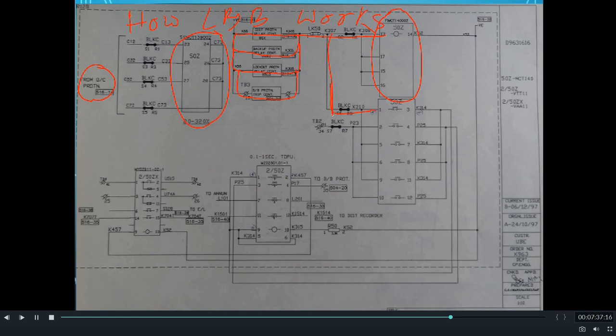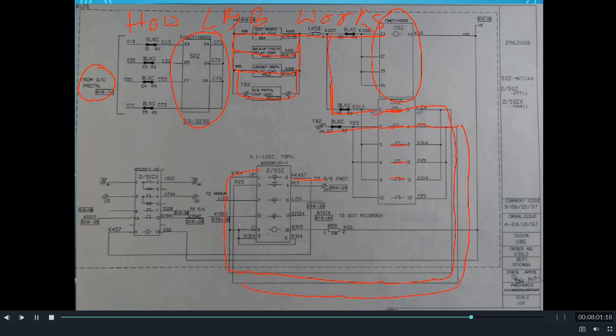Further, looking at the drawing, on actuation of the LBB relay, the auxiliary contacts that are open will get closed. Through these closed contacts, the DC is further extended to the time delay unit of the LBB relay. The output of the time delay unit is further given to the busbar protection. As this is a drawing for a one and a half breaker scheme substation, the operation of LBB will lead to operation of all the remaining circuit breakers — that is, operation of busbar protection is required. However, in different busbar arrangements, this output will be given to the other circuit breakers.